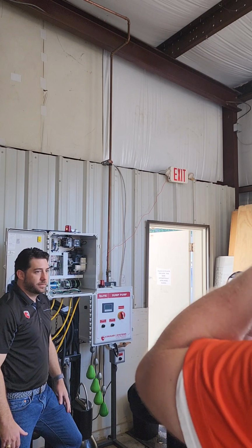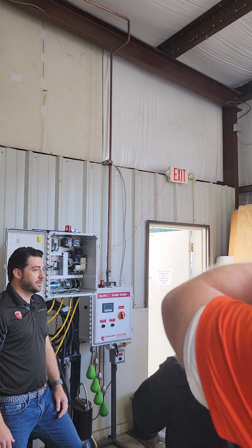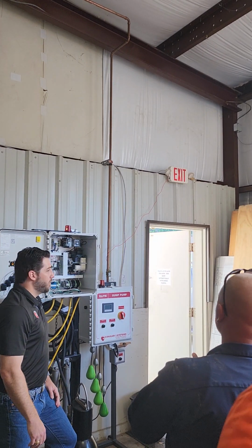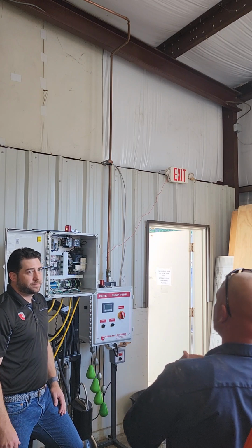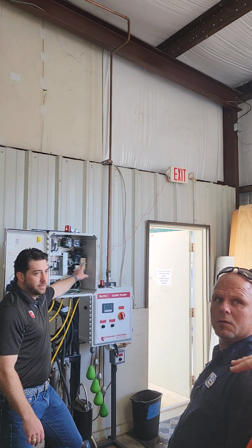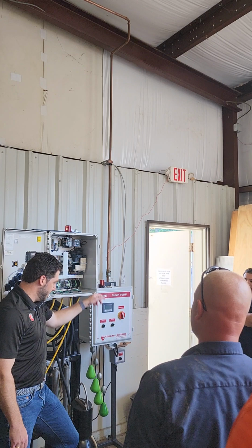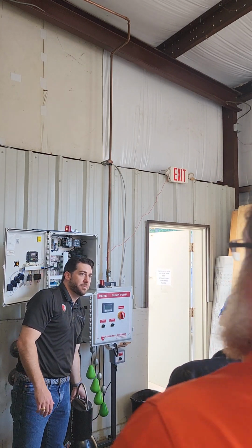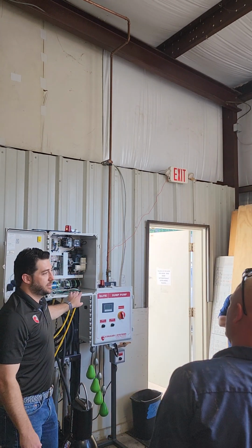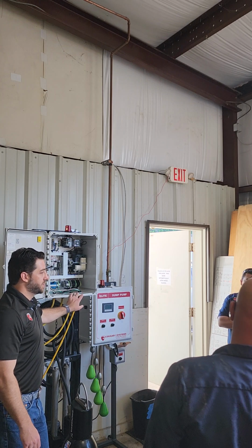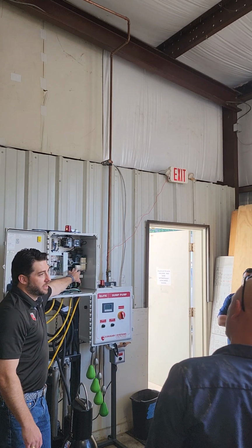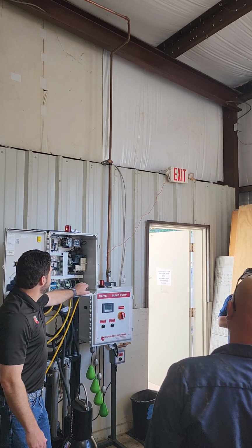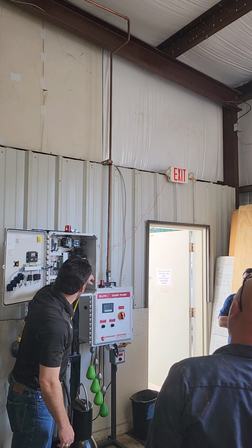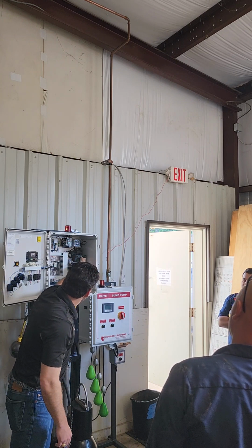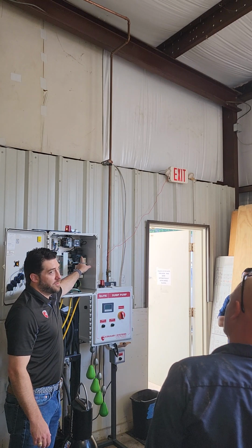That's some Iron Man stuff. There you just put it out, put it in. So the overload is pretty much the amp draw on the pump, correct? Yeah. So you dial these in to whatever the nameplate full load amps, the FLA, on the motor is, and then it'll give you that safety factor built in. These are going to trip to protect the motor, and they have a little indicator on them when it does trip. It'll tell you if it's the overload or if it was a direct short.